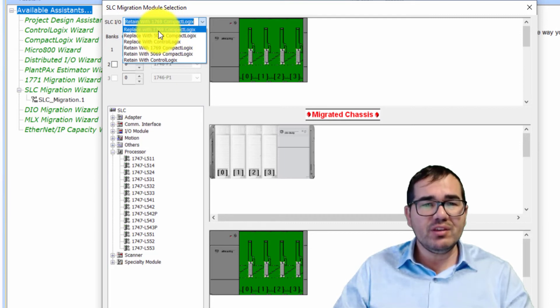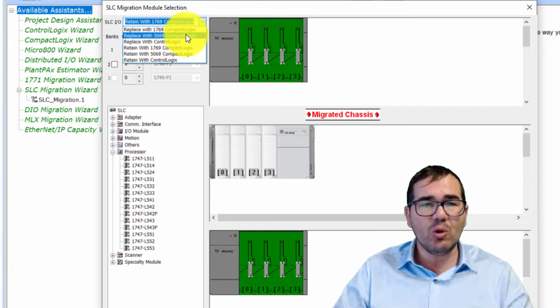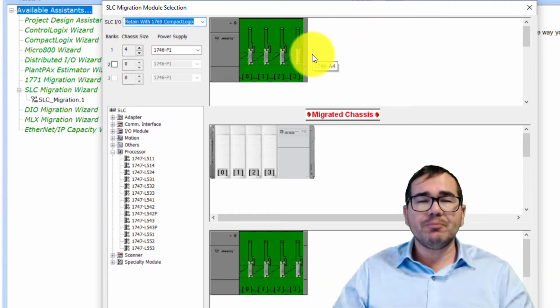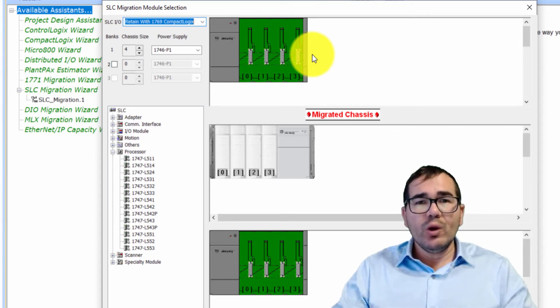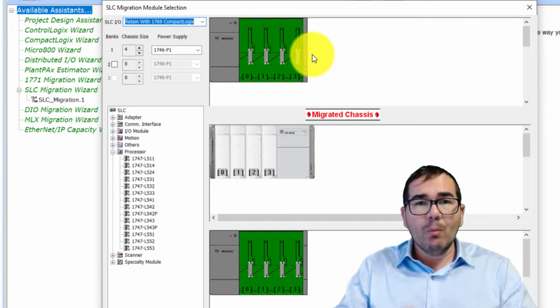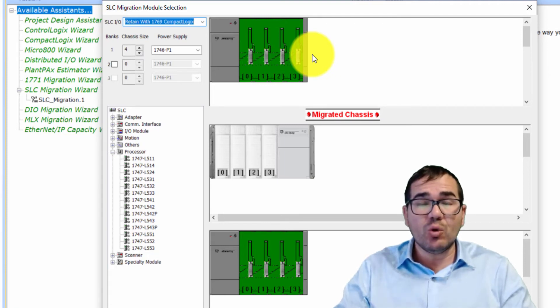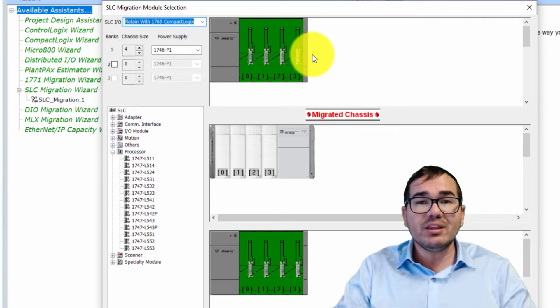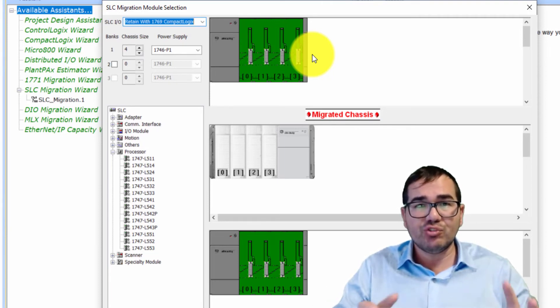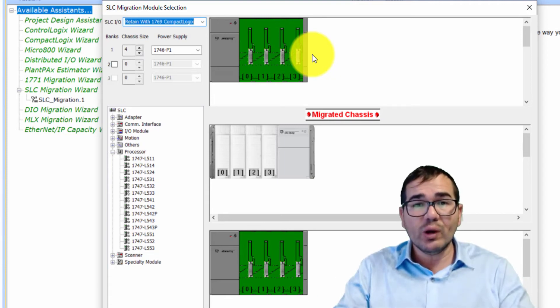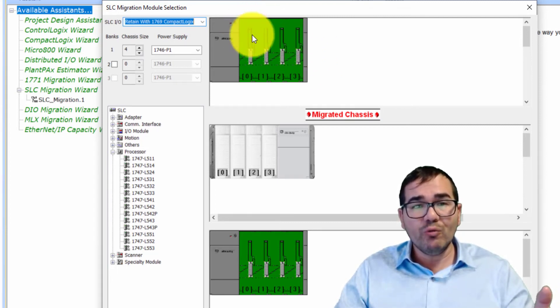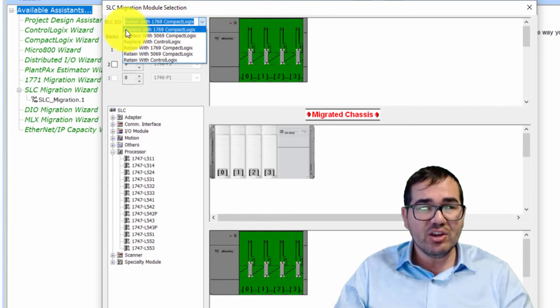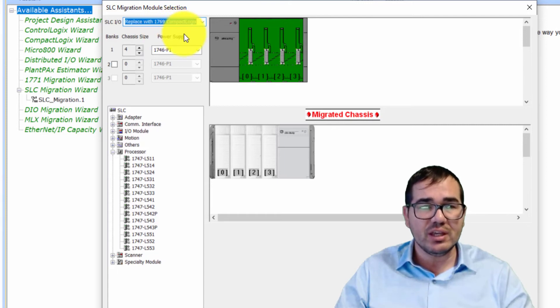We need to choose whether to replace with 1769 CompactLogix, 5069 CompactLogix, or ControlLogix. If you have an old SLC 500, you need to decide: will I migrate to CompactLogix or ControlLogix? For CompactLogix, we have two main families — 1769 and 5069.